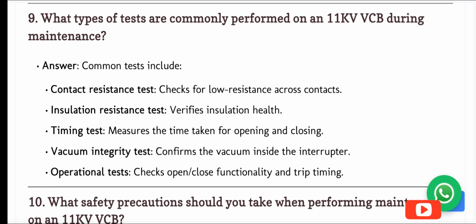Answer. Common tests include contact resistance test: checks for low resistance across contacts. Insulation resistance test: verifies insulation health. Timing test: measures the time taken for opening and closing. Vacuum integrity test: confirms the vacuum inside the interrupter. Operational tests: checks open-close functionality and trip timing.